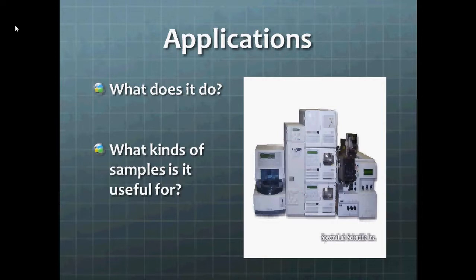It's very sensitive and extremely selective, much more selective than the traditional quadrupole mass spectrometer. It can also be paired with many different types of ionization techniques and a plethora of separation techniques. All of the different combinations of ionization techniques and separation techniques means that the triple quadrupole mass spectrometer can analyze a huge range of different analytes. As you'll see over here on the right, we have an HPLC hooked up to a triple quadrupole.